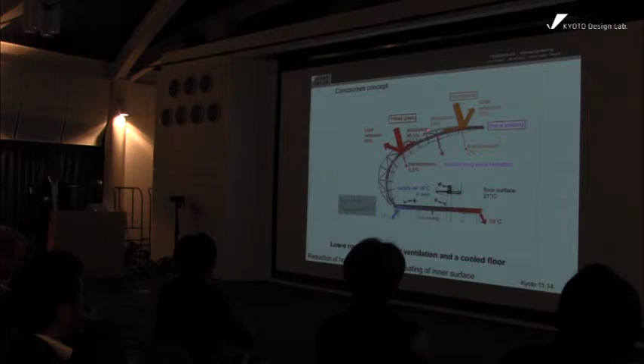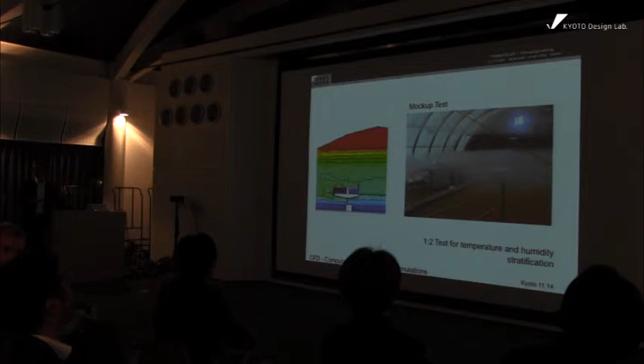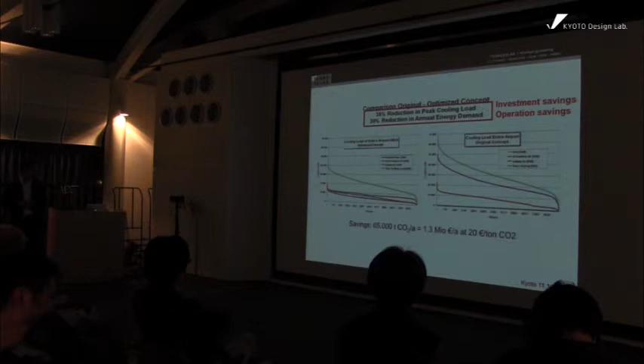You can see it here in the simulation. Very hot there, cold there, no condensation there, and we reduce the energy consumption dramatically. This was a mock-up test also. And here you can see what the result was. We reduced the peak cooling load by 35% and the energy demand by 30%. Only by changing the energy concept, but with the old design. That was very important for our company at this time, to show the architect this helps your design, and this is not a restriction for your design.